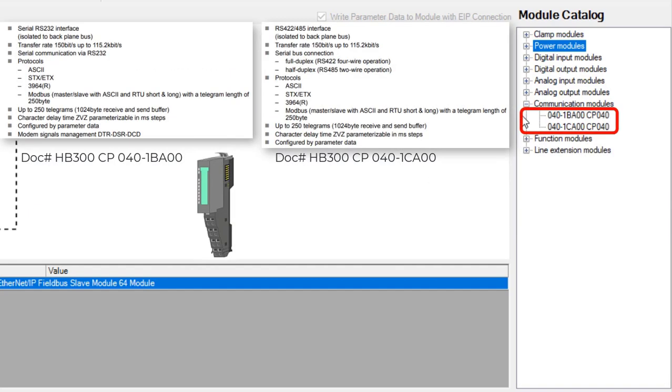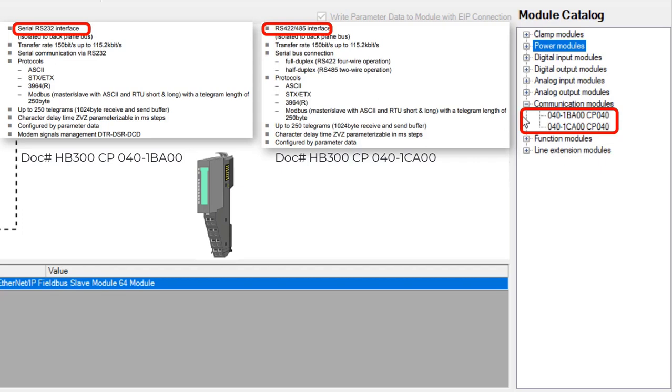Communication slices are also available on the SLIO system. The serial interface slices allow the SLIO device to communicate with RS-232 and RS-422/RS-485 compatible devices. These protocols are commonly used to communicate with legacy or simple machine devices.